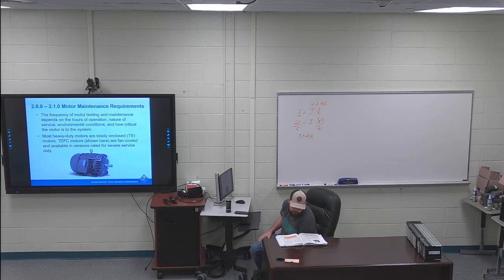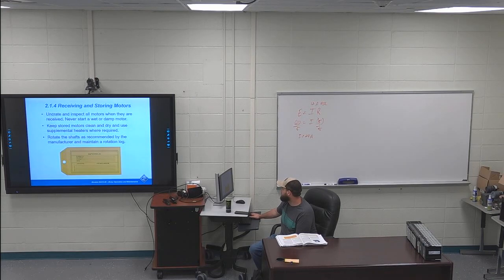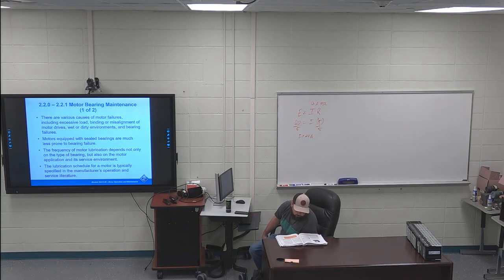Motor bearing maintenance, 220. Last sentence of 220 is highlighted: motors equipped with sealed bearings are much less prone to bearing failure. Sealed bearings work a lot better, but they're not always practical for some motors. 221, frequency of lubrication. First sentence is highlighted: the frequency of motor lubrication depends not only on the type of bearing, but also on the motor application and service environment. So where your motor is, and how often you can get to grease it.